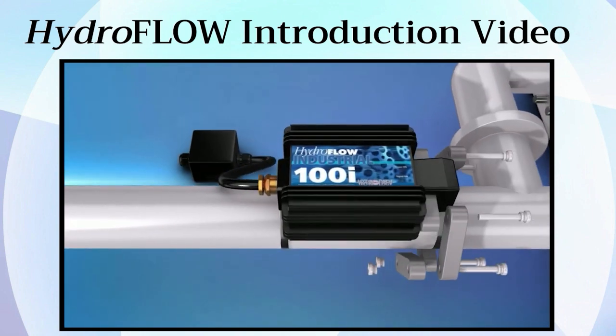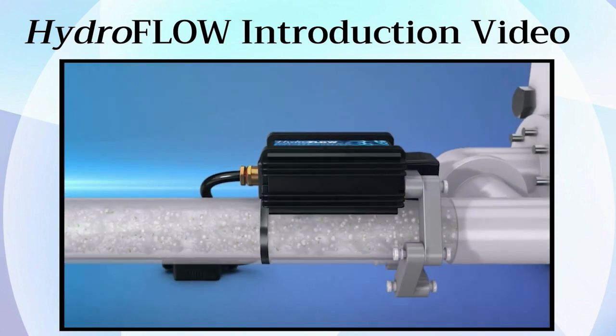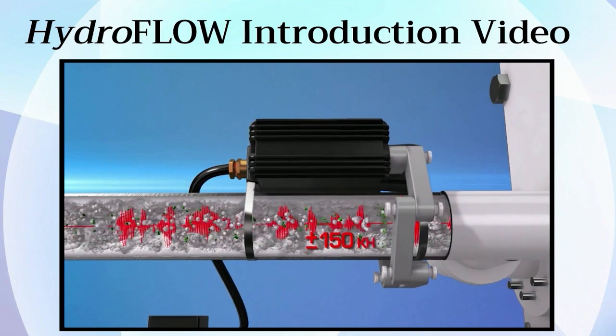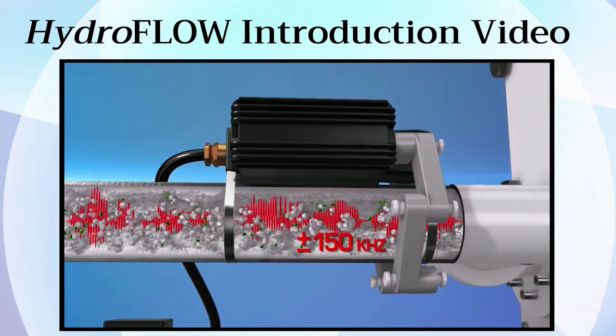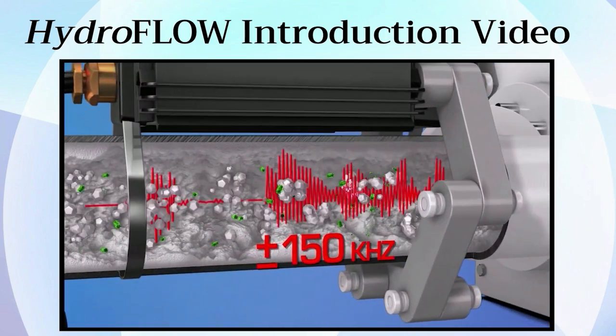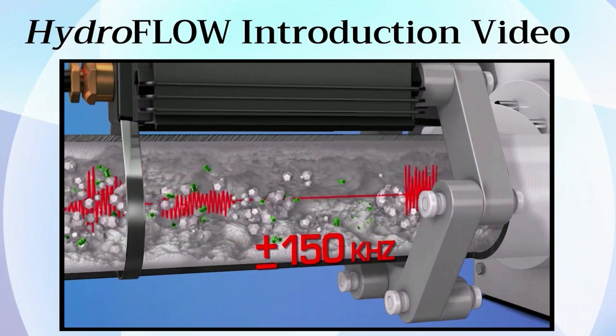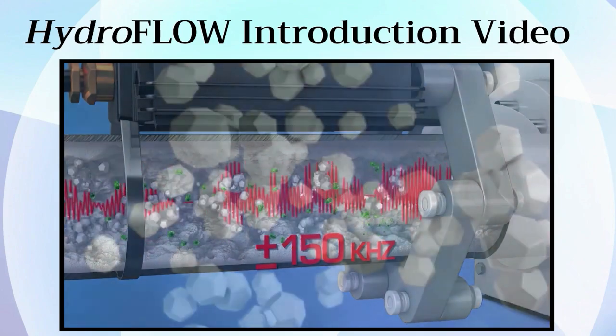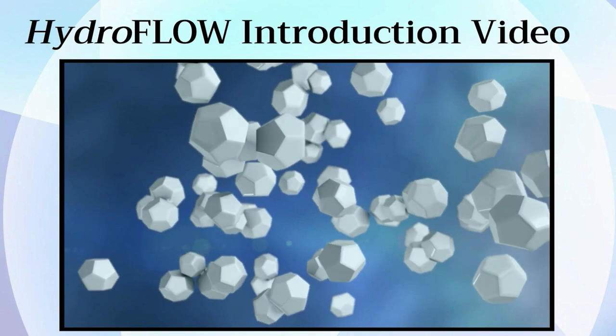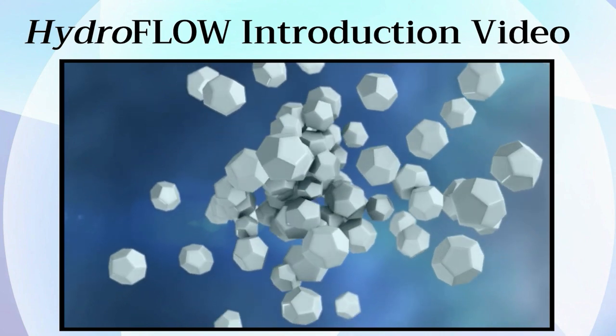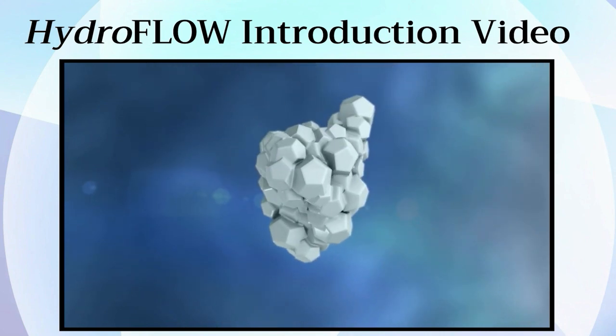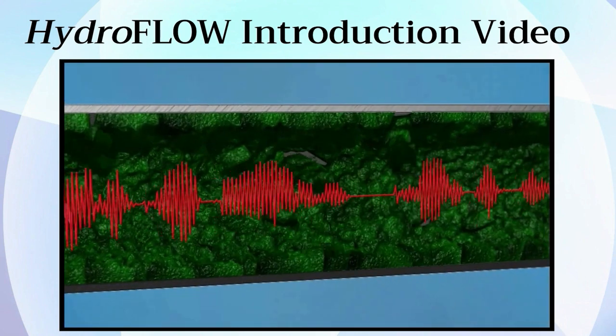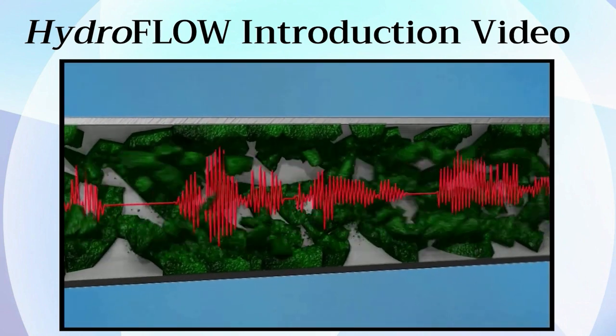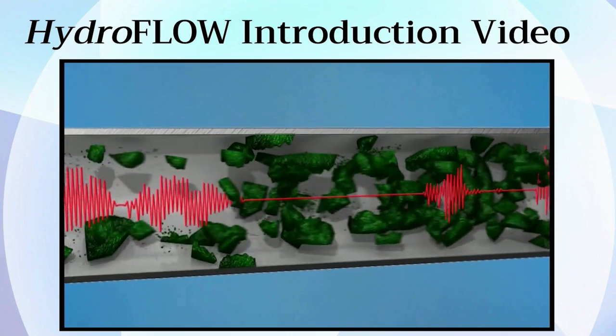The HydroFLOW water conditioner applies an electric signal of 150 kHz throughout the piping system, causing the ions to form clusters. When supersaturation occurs, the clusters precipitate out of the solution and form stable crystals, which do not adhere to piping and equipment. Additionally, the signal agitates the biofilm colonies, causing them to detach and flush out.